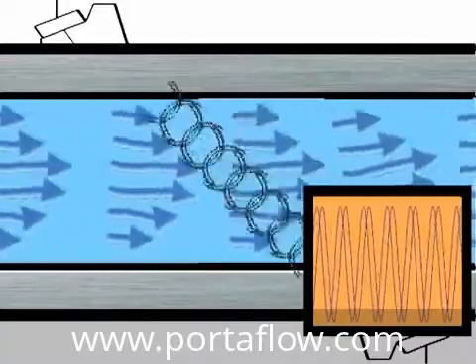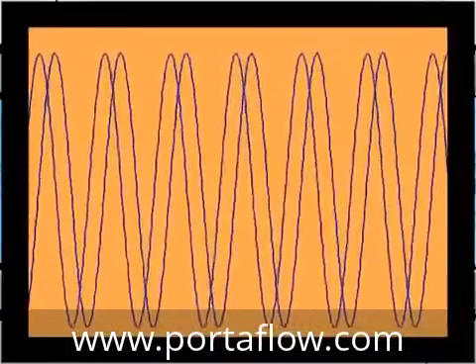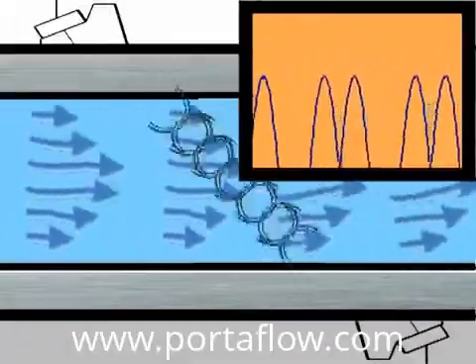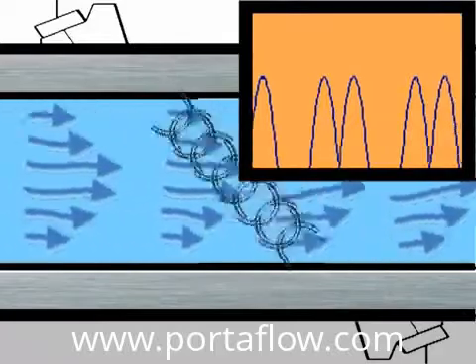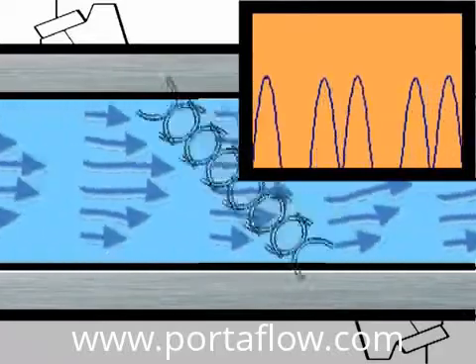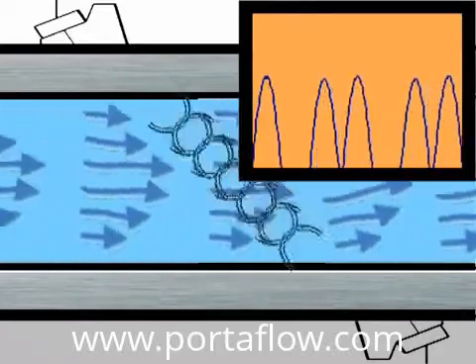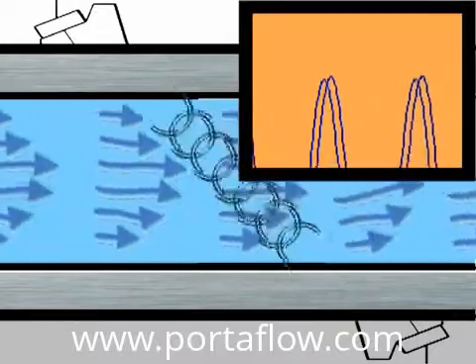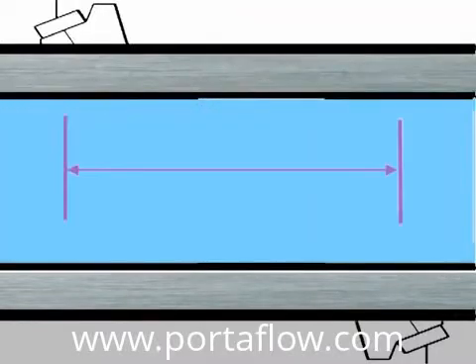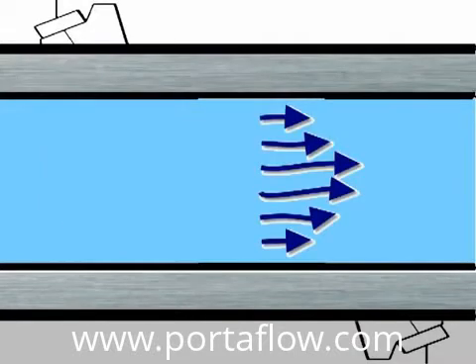To measure the difference in arrival time, we simply look at the phase shift between the two signals. This phase shift difference is directly proportional to the speed of the liquid in the pipe. This relationship is a function of how far apart the transducers are and the flow profile of the liquid in the pipe.